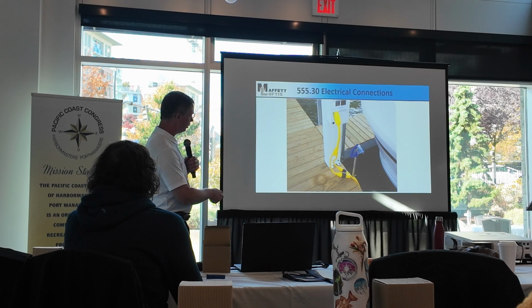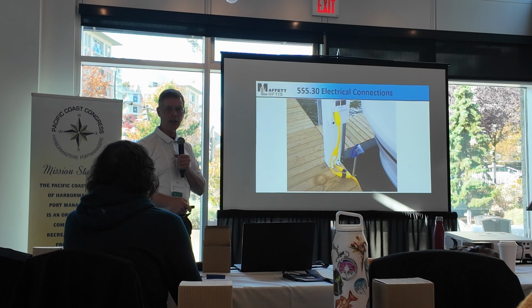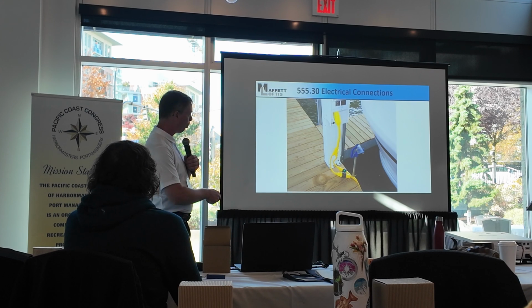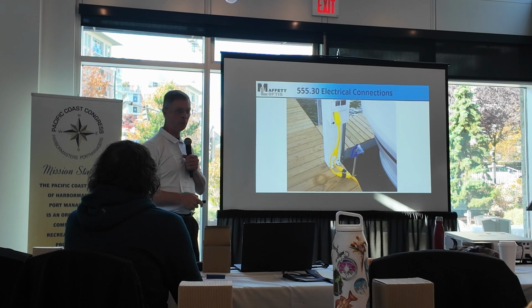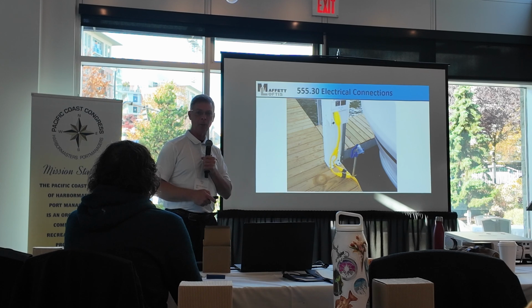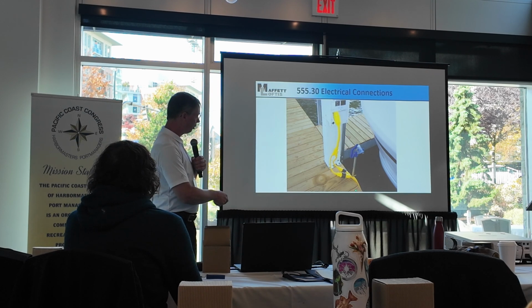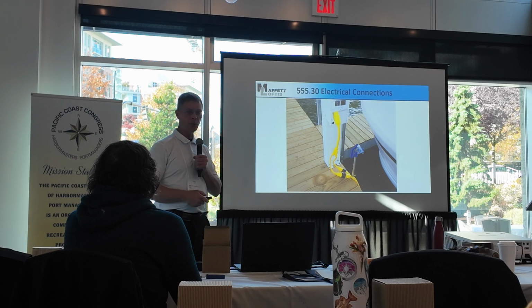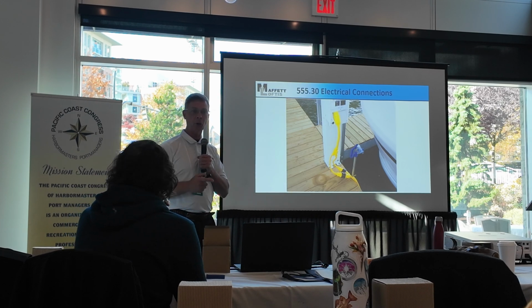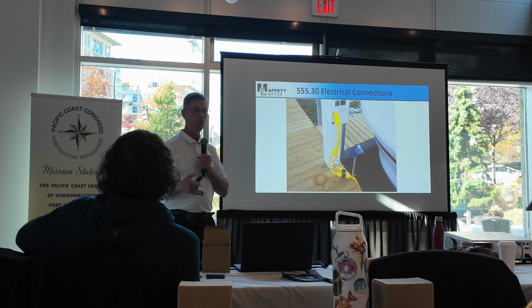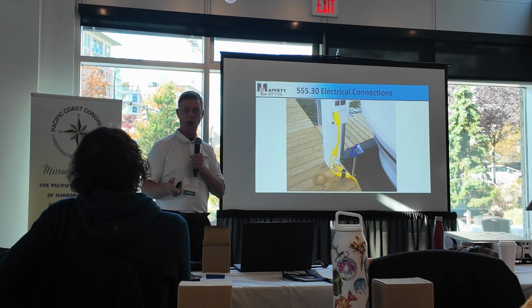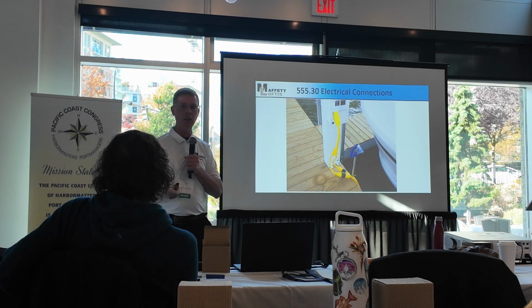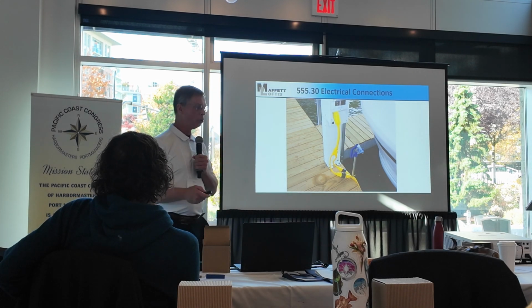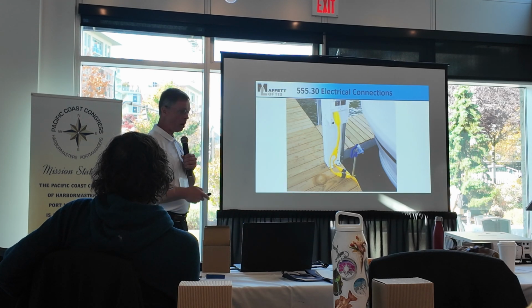So what are these down here? Number 10, 30 amp wire. So you've got 30 amp wire protected with a 50 amp breaker. Do you think that's a problem? Can it be a problem? Absolutely, it can be a problem, because you could have an air conditioner and a water heater, and that could be pulling 48 amps on a number 10, 30 amp rated wire, overheat, melt insulation, cause a fire, cause shock, and it's happened before, many times. Okay? So that adapter is not valid.